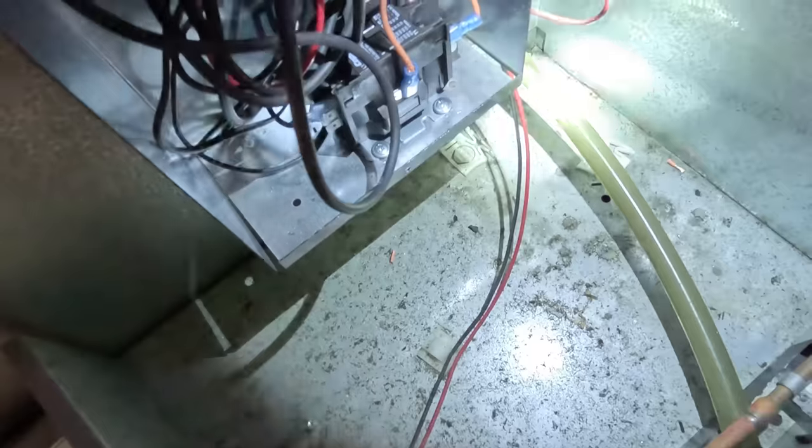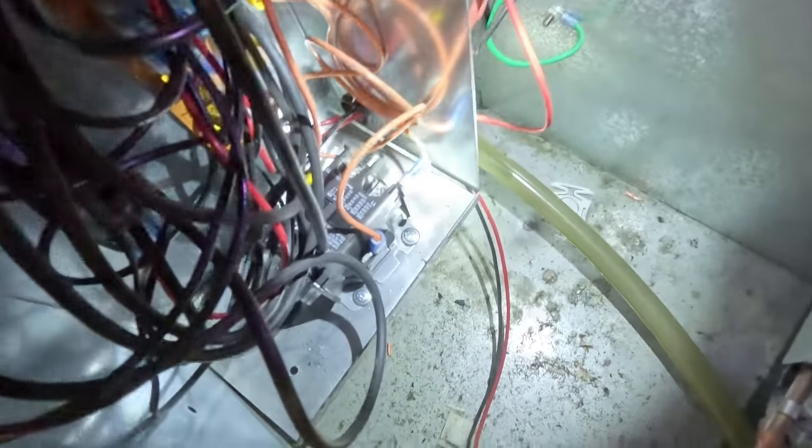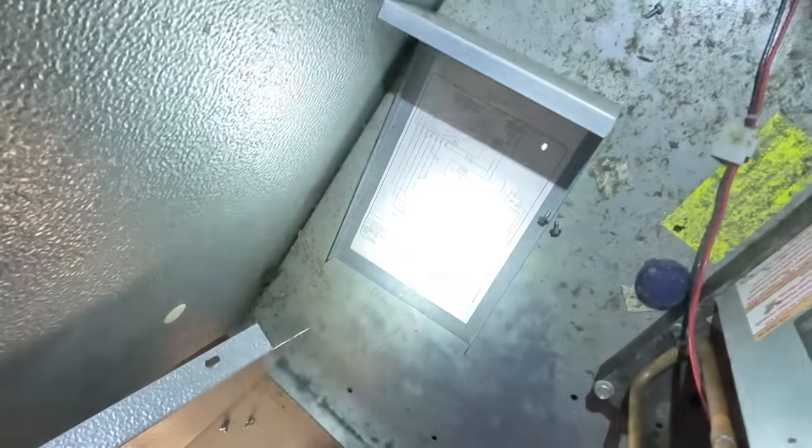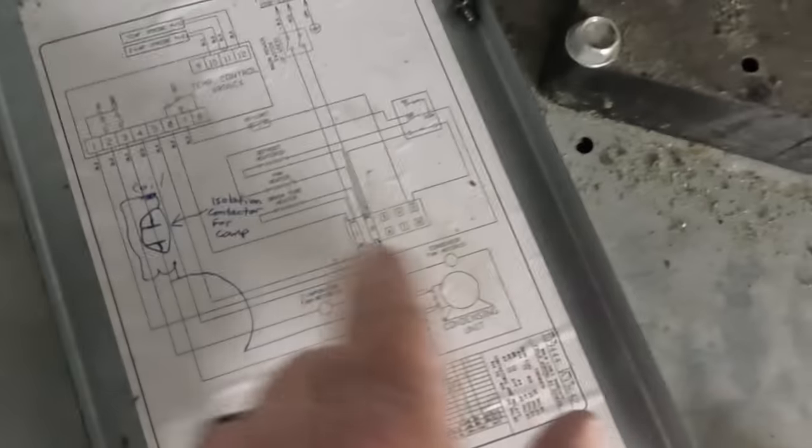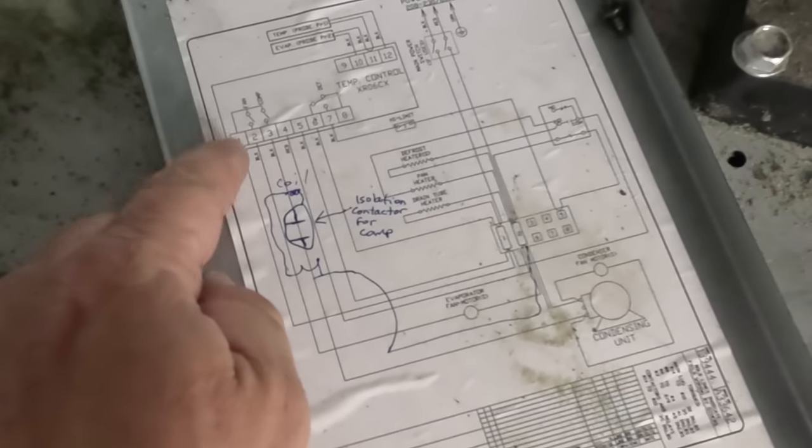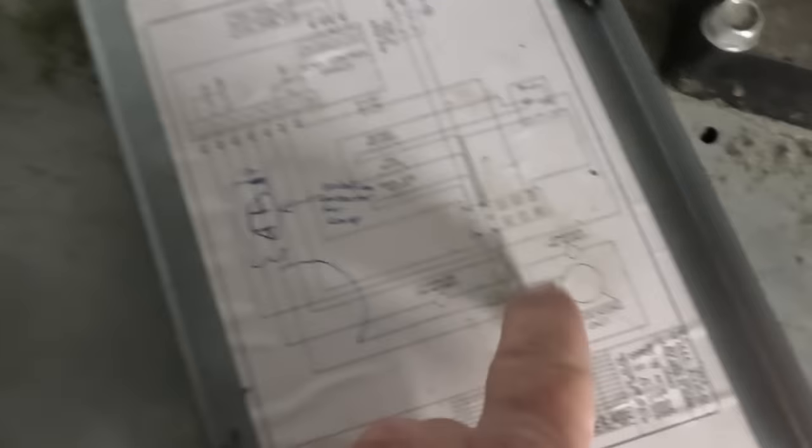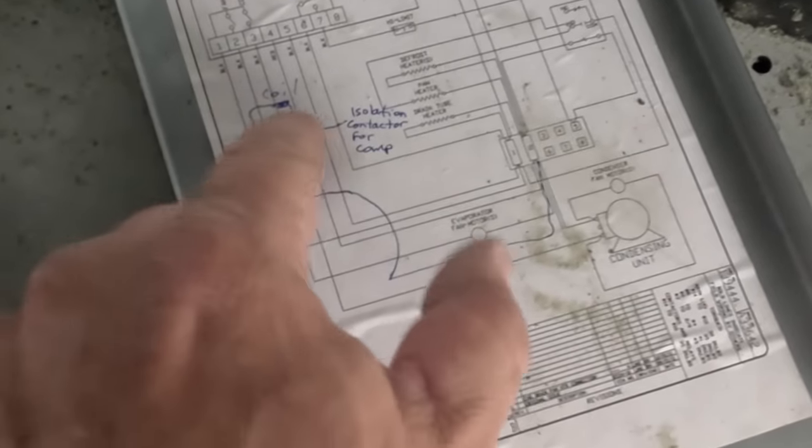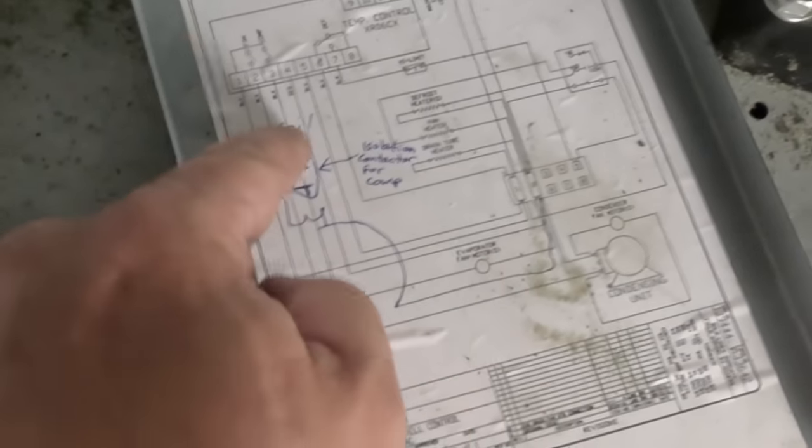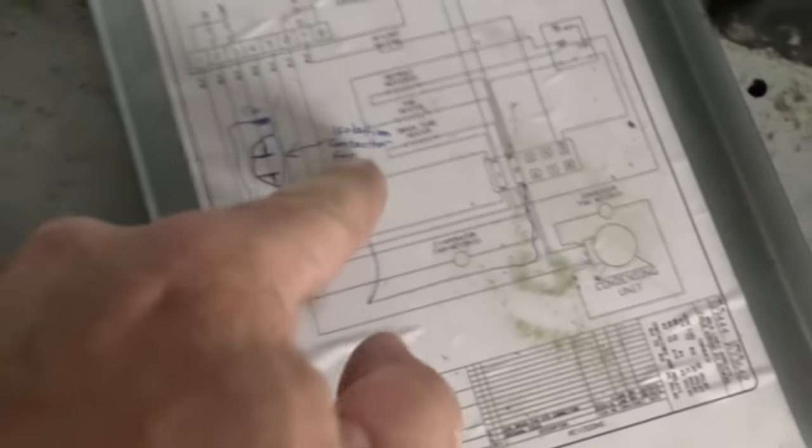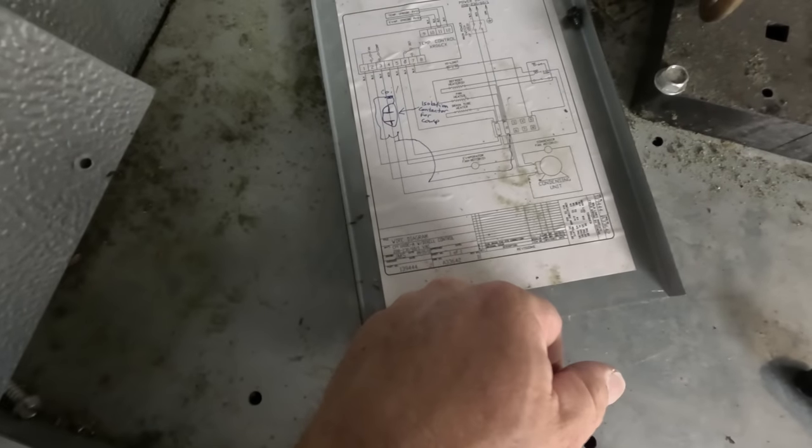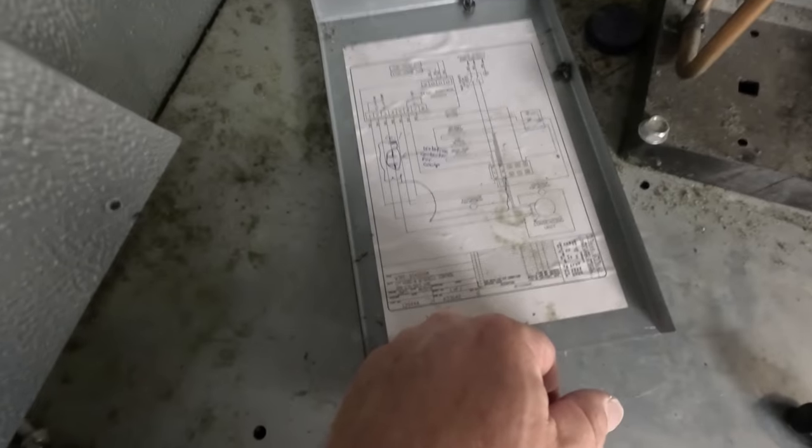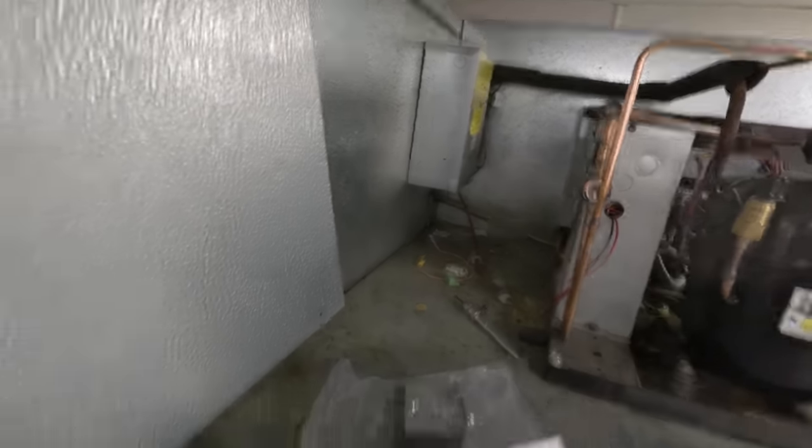We've got it mounted down there in the bottom with two screws. All the wires are clean and clear away from all the metal. Everything's ran through the eyelets. Everything's back to the same. We're going to mark in here what we did on the schematic. It's kind of hard to see here, but so number one here was power going to the controller. So opposite of that would be two. That is going to be what comes down and goes over to the coil. The one coil gets powered off the side of the compressor. So that's your coil. It's really in there as your normally open switch. That's the isolation contactor. There you go. Simple as that. Most people would be able to figure that out without the wiring. They wouldn't have just did it just to be safe in case somebody that doesn't have as much experience.